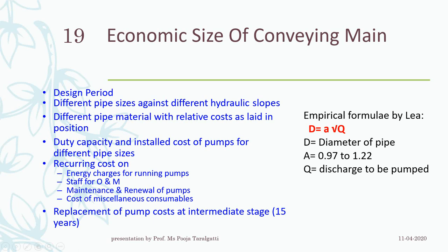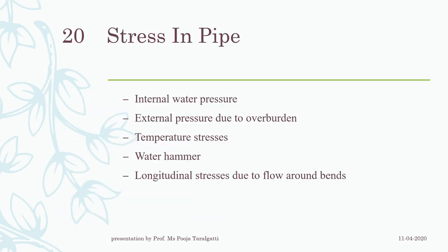For calculation, the empirical formula by Lea gives the main diameter as D = A × √Q, where Q is the discharge. This is how you can go for the calculation and consideration of the economic size of the conveyance main.